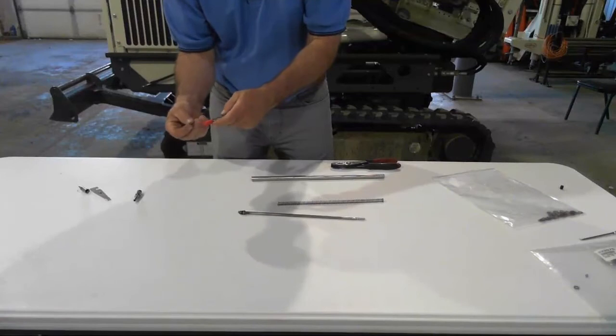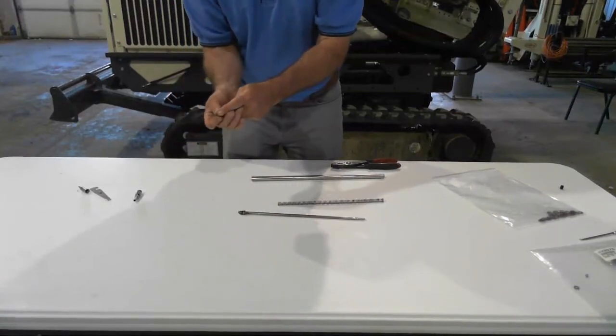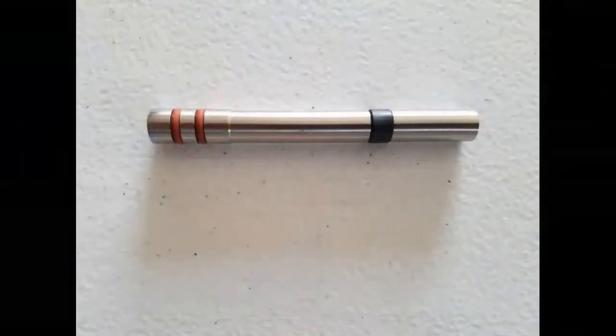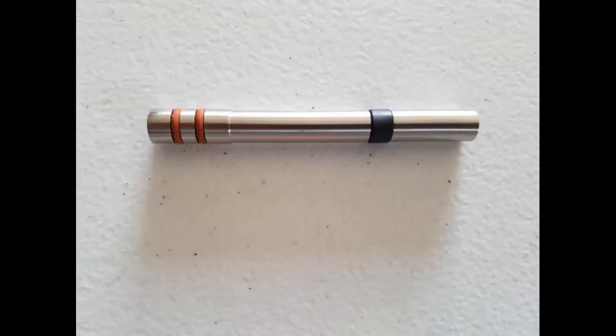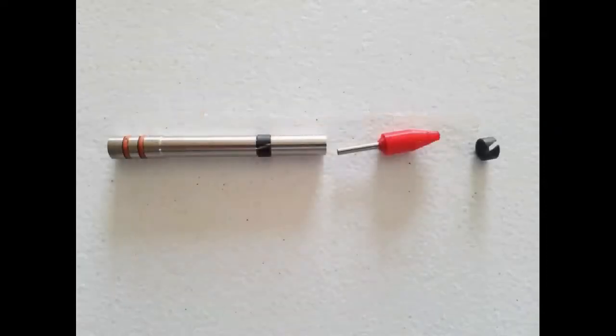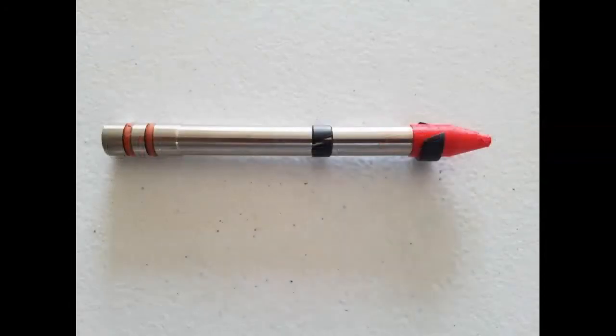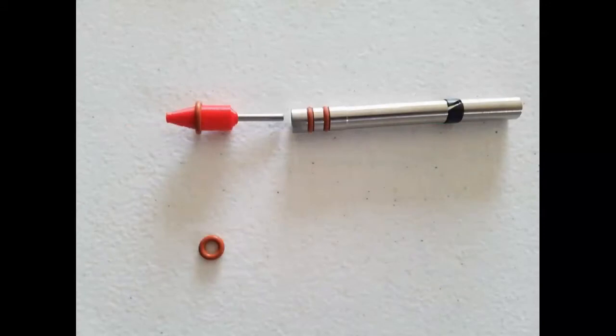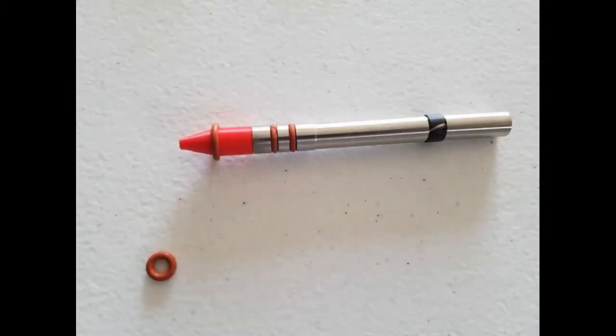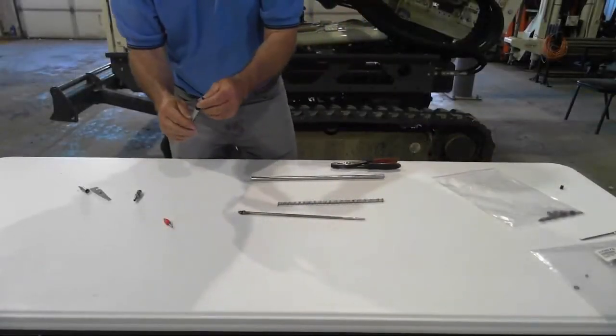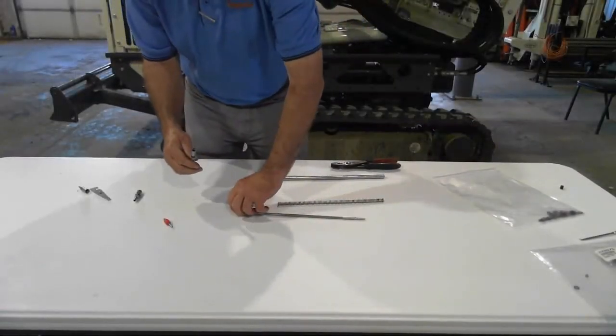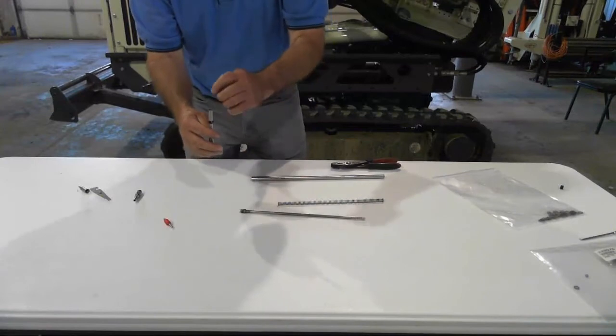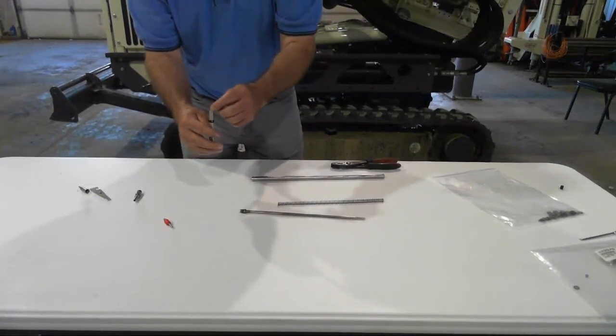Then we'll take a look at the piston and these components we're installing. Here is the piston with the two O-rings on the left and the wear ring on the right. And here's the installation tool. When we slide that wear ring on there, it'll just go right over onto that piston, and the same thing with the O-rings. The piston has a ball check section on it which will allow it to move water up the pump and into the tubing without leaking back out.